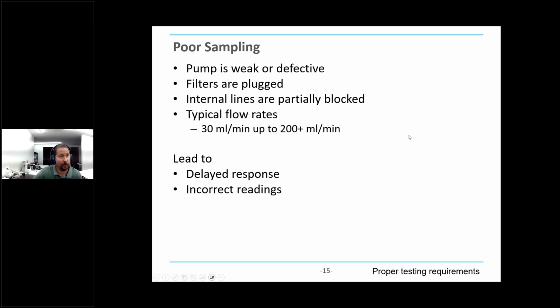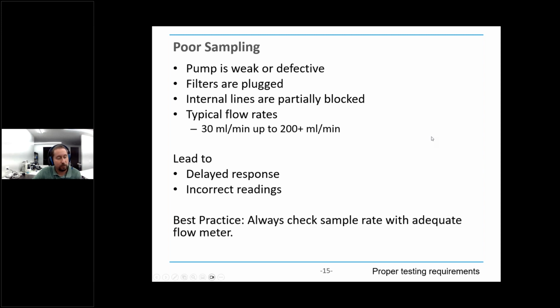You can also get incorrect readings. The gas monitors have a CO2 sensor built into them, and they need a certain amount of flow just to work. And if that flow is low, then that can be a problem. And so the best practice for this really is to always check your sample rate. But it's interesting, in our research, what we found is a lot of people may test their sample rate, but they don't test it with a flow meter that's adequate for the job. We've seen people use their vent testers to try to test these very small flow rates, and they're just not sensitive enough. So you got to make sure you have a flow meter that works properly.